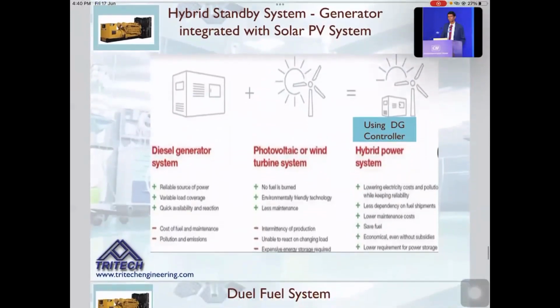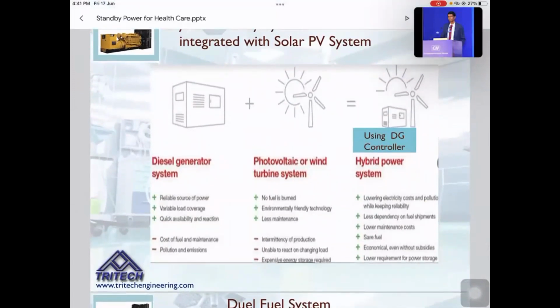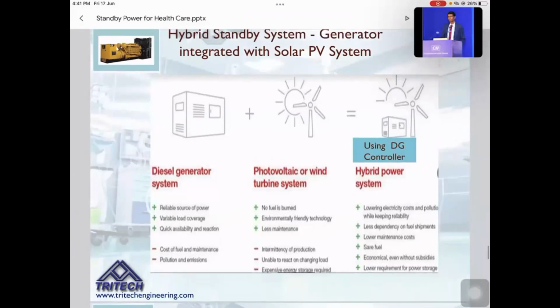Then another aspect is whether to connect solar power in the case of a DG set. We always recommend connecting the solar power supply system while your DGs are working, because it drastically reduces the fuel consumption of the DG set. The important thing is that the DG controllers should have the capability to handle EB power, DG power, and hybrid power with EB, DG and solar. Most of the new generation manufacturers of DG controllers provide the hybrid system, which will save you a lot of cost on diesel consumption. This is one aspect I wanted to highlight.